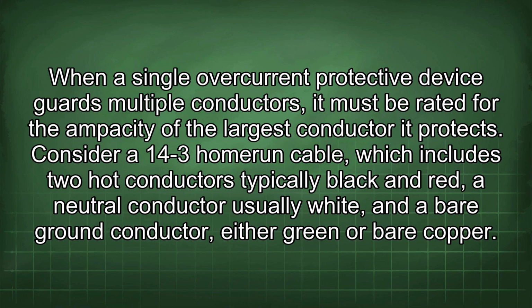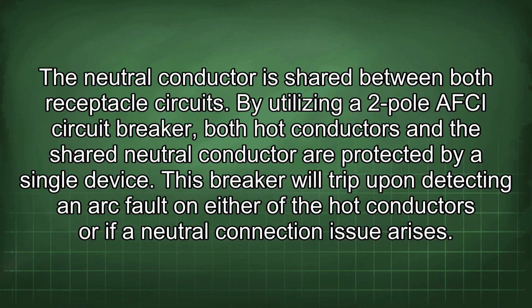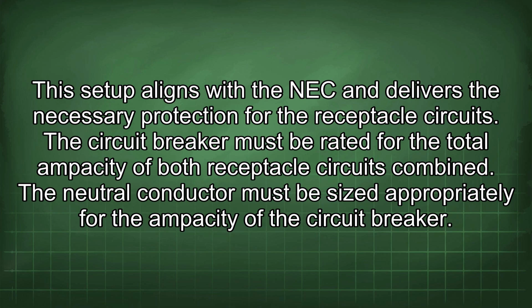Consider a 14-3 Romex cable, which includes two hot conductors, typically black and red, a neutral conductor, usually white, and a bare ground conductor, either green or bare copper. The neutral conductor is shared between both receptacle circuits. By utilizing a two-pole AFCI circuit breaker, both hot conductors and the shared neutral conductor are protected by a single device. This breaker will trip upon detecting an arc fault on either of the hot conductors or if a neutral connection issue arises. This setup aligns with the NEC and delivers the necessary protection for the receptacle circuits.